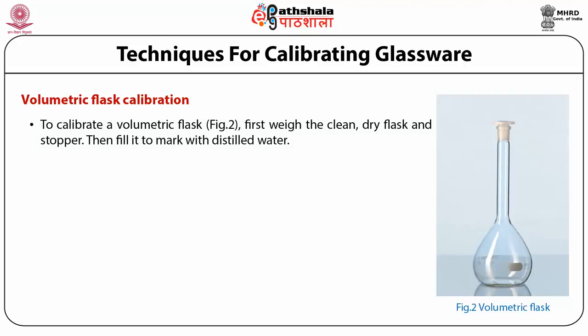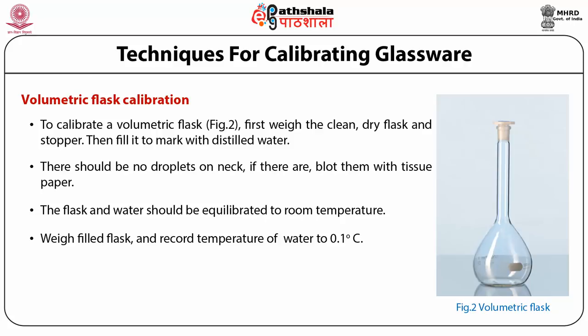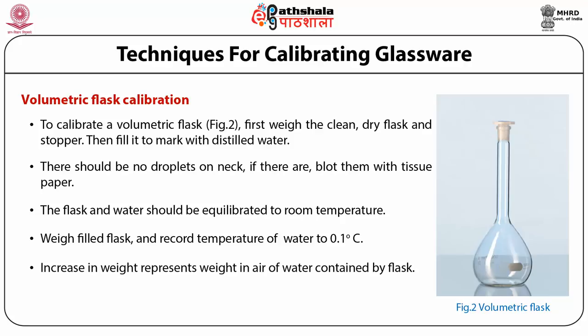Now we discuss techniques for calibrating glassware. For volumetric flask calibration, first weigh the clean dry flask and stopper, then fill it to the mark with distilled water. There should be no droplets on the neck; if there are, blot with tissue paper. The flask and water should be equilibrated to room temperature. Weigh the filled flask and record the temperature of the water to 0.1 degree centigrade. The increase in weight represents the weight in air of water contained by the flask.